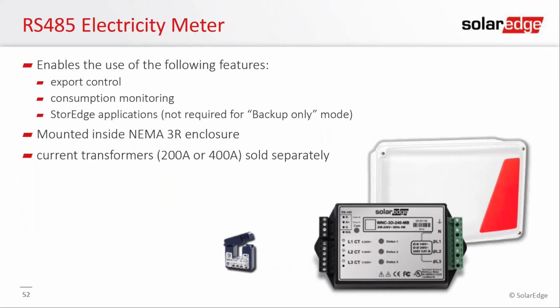The electricity meter, I see a lot of people installing it next to the inverter. There's no need for that. The best place to install the StorEdge electricity meter is out next to the service entrance, or wherever the CTs need to go, because that's going to be your limiting factor for distance, the CTs. We sell the CTs separately, and basically it's a split core CT that wraps around the feeders of the service entrance and measures the magnetic field. By the magnetic field, we can see how much current is coming and going from the home. So now we can see, okay, do I need to discharge the battery? Do I need to charge the battery? Do I need to curtail the inverter, depending on what your grid requirements are?